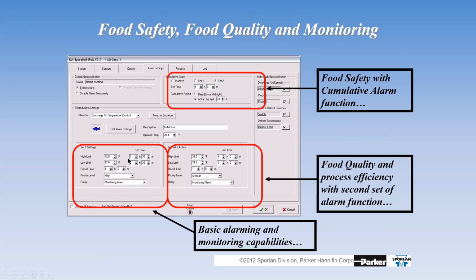You're never going to get an alarm, but this could cause a serious food problem in the store by letting this case go all the way to 50 degrees. So that's why, Nate, we talk about individual usernames and passwords. And I'm sure Loblaws probably does this already, but we don't want everybody and their brother going in and messing with these set points. It can cause a serious problem with food quality and bacteria growth, okay?